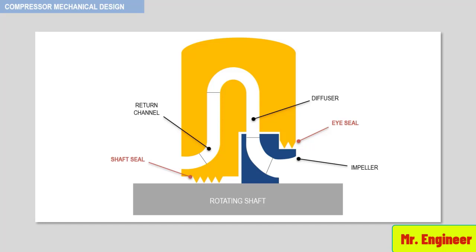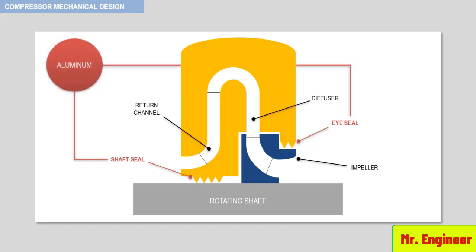Interstage seals are usually manufactured of aluminum to ensure that contact with the rotor does not result in an external excitation to cause vibration. However, certain gases and saturated gas mixtures require that alternative materials be used.